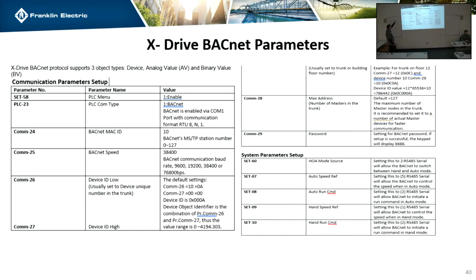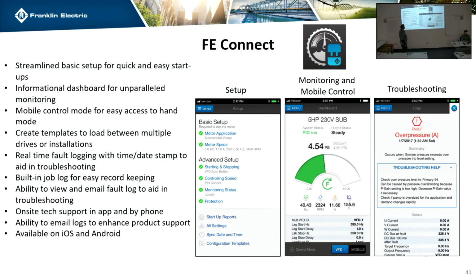And then here are the parameters that you'll see from the drive. This is just compiled from the manual. We have a quick start that shows you how to set up BACnet, and it goes through the wiring and all the options, and I'll show that to you. Just like Modbus, it's got a bunch of defaults in there that should be pretty normal for your industry standards, but depending on who you're working with, they'll use something else and they'll need to change it. Go ahead and go to the next one.